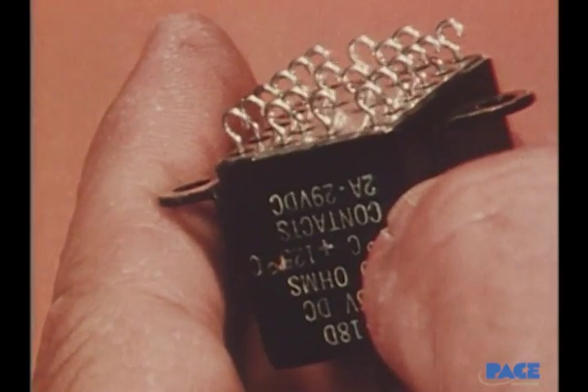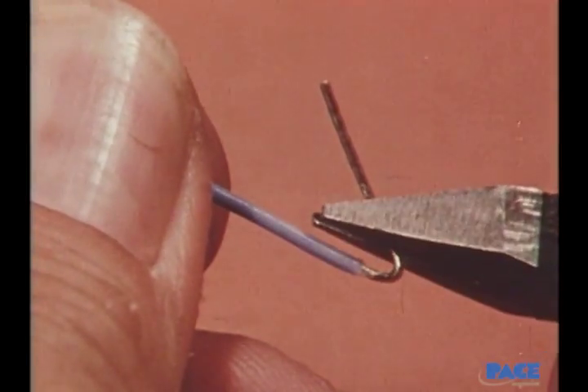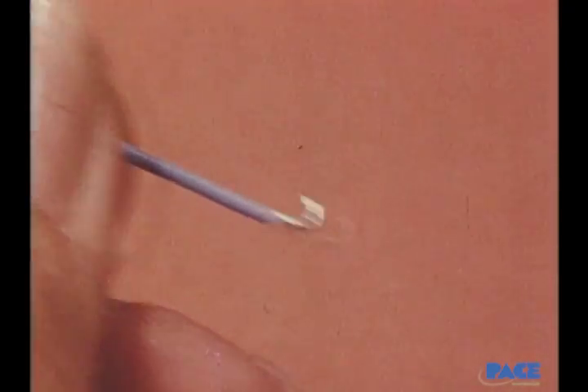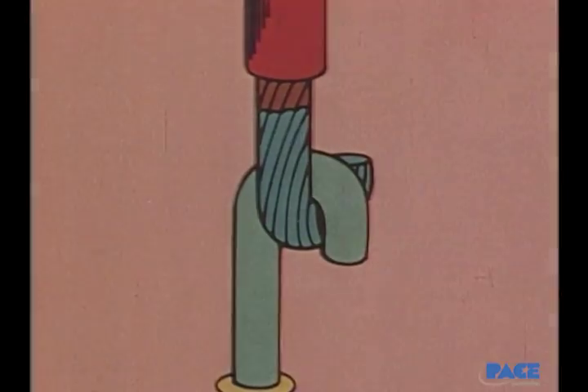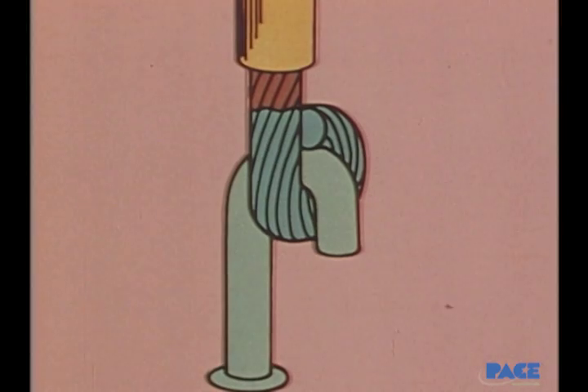Another type of terminal is the hook terminal, often found on hermetically sealed relays. The wire wrap should be at least 90 degrees. This one is 180 degrees. For repair work, a 270 degree wrap is recommended.